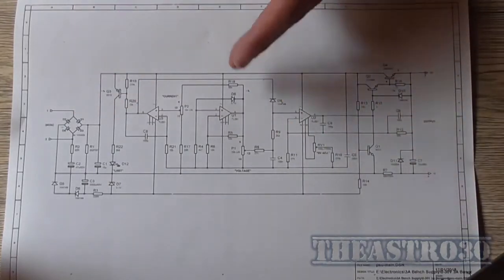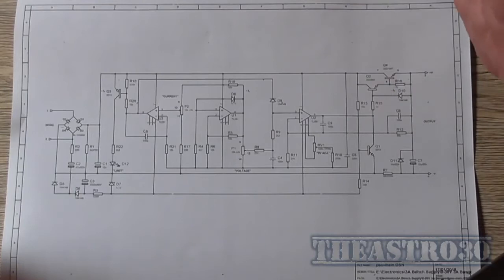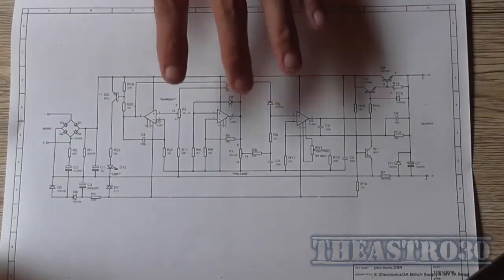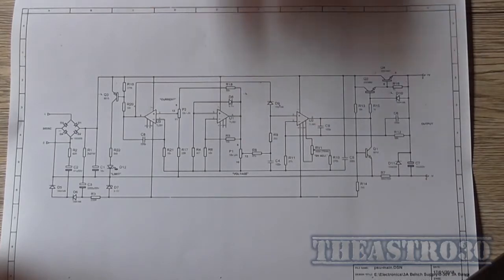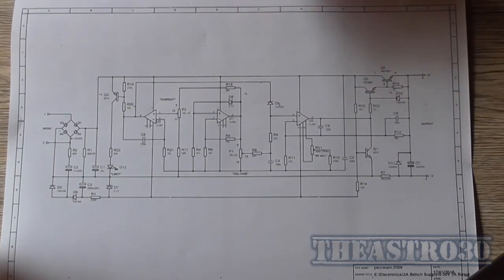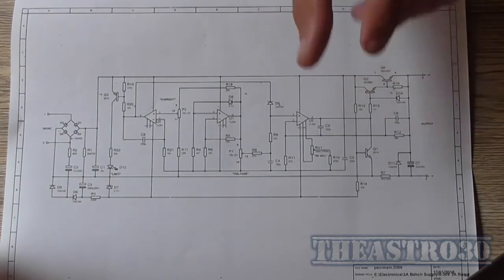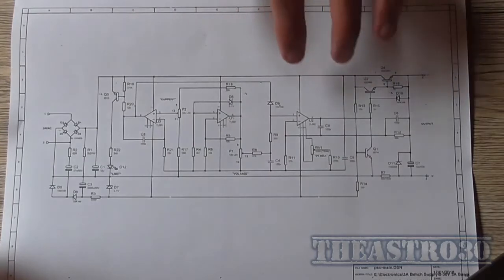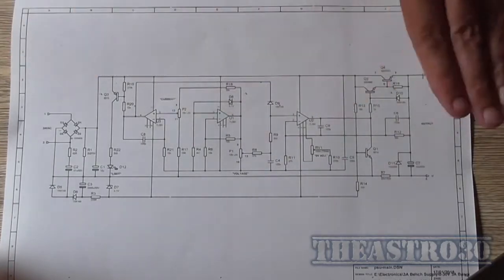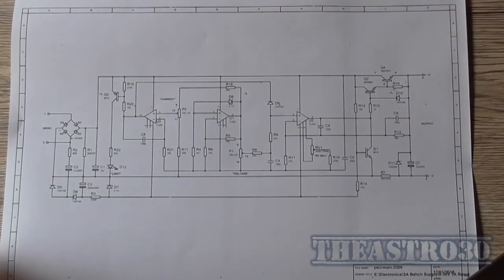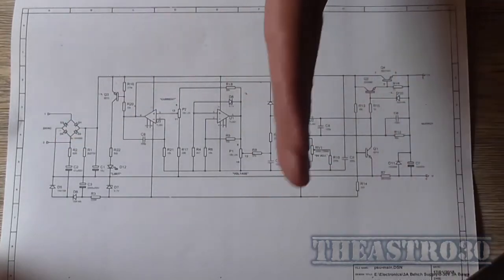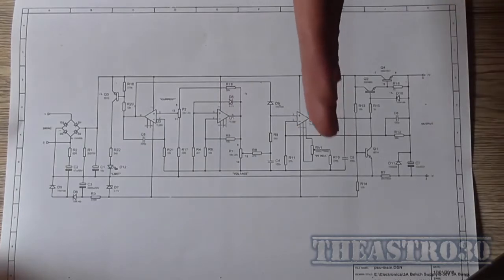In a voltage regulator, current adjustment comes first, which is then series passed to the next stage, the voltage adjustment, which then passes on to the regulation circuit and the output transistors. For example, say the current was set for a 1 amp limit and the voltage set at 10 volts, and you're at 1 amp. If you increase the voltage knob while in constant current mode, the voltage won't increase because it will try to bring it down to keep the current flow at 1 amp.